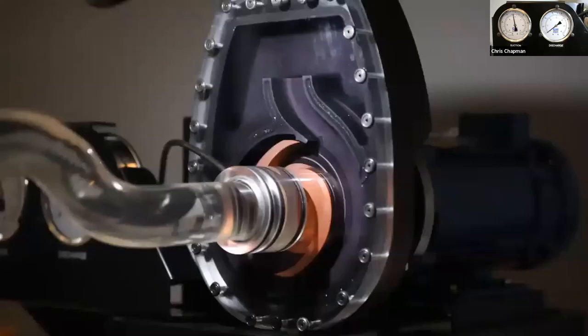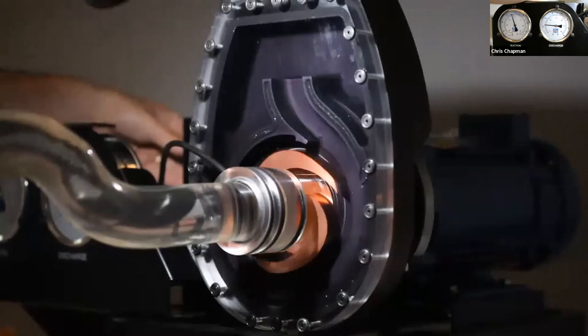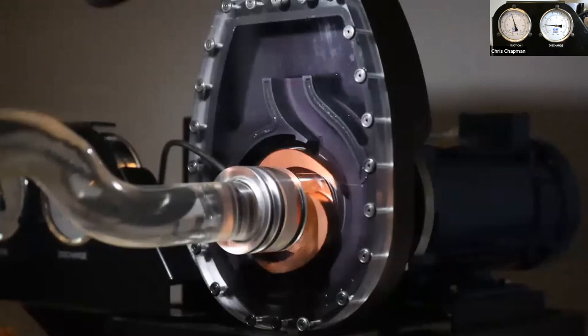Starting the pump again at the same 1,750 RPM with the valve unchanged — we're getting the same gauge readings: plus 12, minus 5. We also have a flow meter to double-check: the flow meter reads about 28 gallons per minute, and we predicted somewhere in the 25 to 30 range, so we're pretty close.